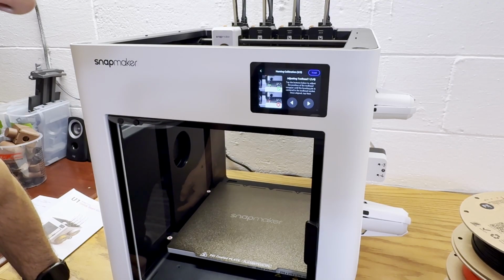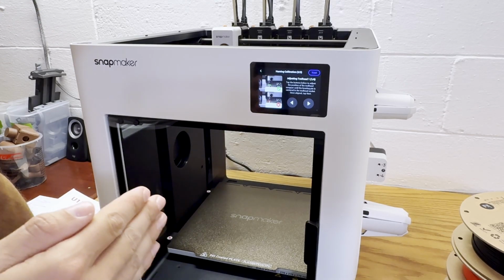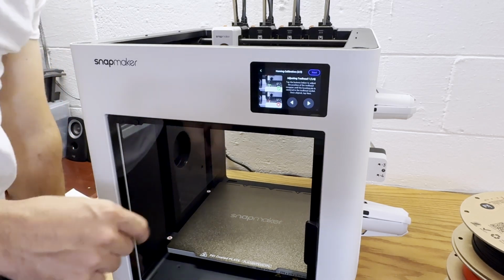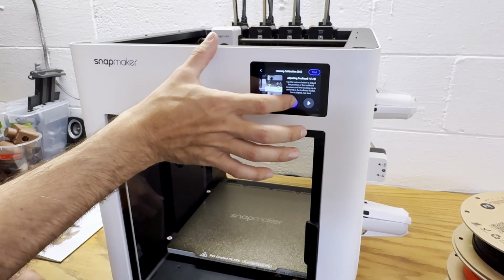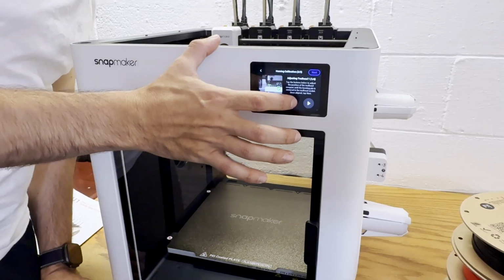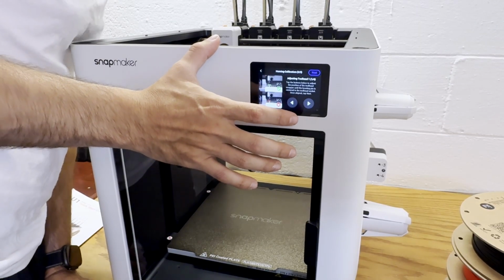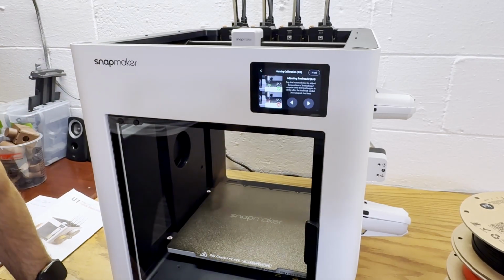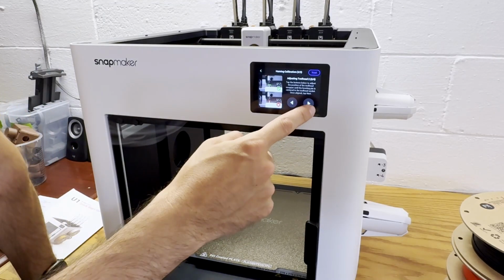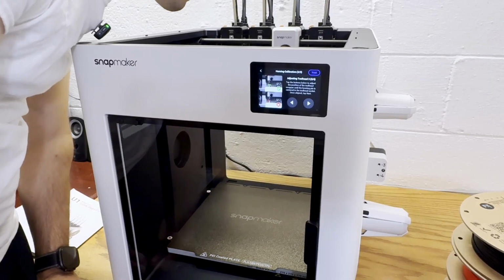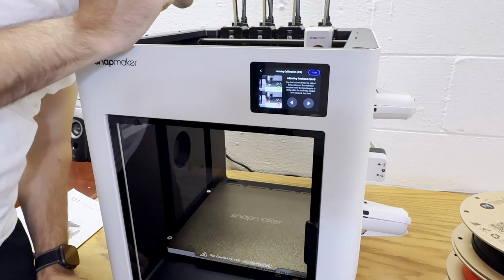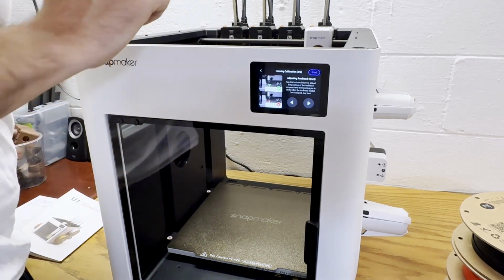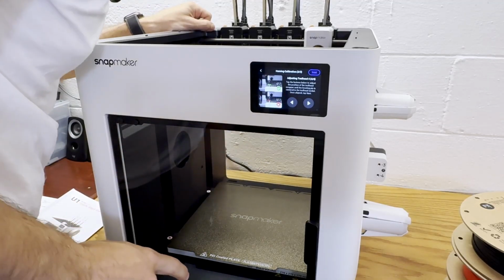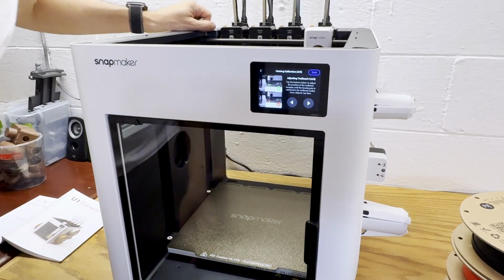It says adjusting tool head. Tap the buttons below to adjust the position of the tool head swapper until the locating pin is centered in the tool head socket. Once aligned, tap next. All right, so we want to make sure it's centered on that hole in there. And mine actually already looks pretty good. I'm going to go just a smidge left. That looks pretty much dead center, and I'm going to hit next. That one already looks pretty good. I'm going to hit next. That one also looks good. And this one looks like it may be a little bit to the right, so I'm going to move it left. And one more. That's good.